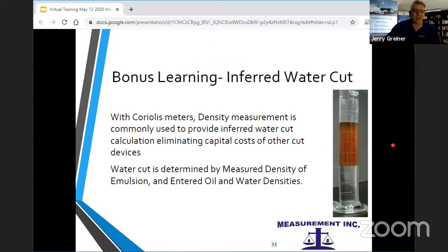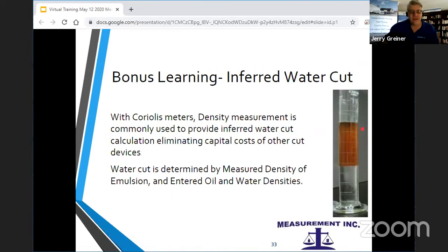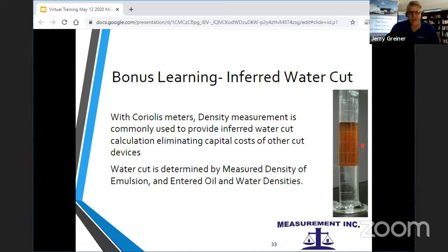We did learn something else though at the same site. We got a bonus learning out of this. It concerns water cut. Coriolis meters measure the density, and they commonly use that to come up with a water cut percentage. Your oil is lighter, your water is heavier. If you know the water density, you know the oil density, and you know the actual density, you can determine, by math, what that water cut is.